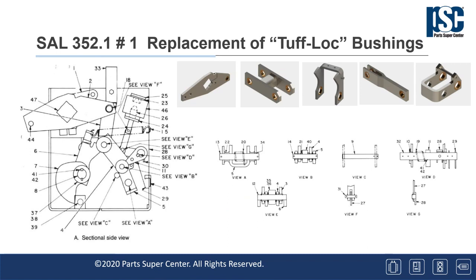This change was introduced into production on breakers manufactured 1974 and later for all Tuff-Loc bushings with the exceptions of those in the prop. The prop is the middle photograph on the top of the slide. This advisory is recommended to be added during the next breaker overhaul since it's a significant amount of work to change these out. The modification involves removing the Tuff-Loc bushings from most of the links, latches, and pawls and pressing in new bronze bushings.